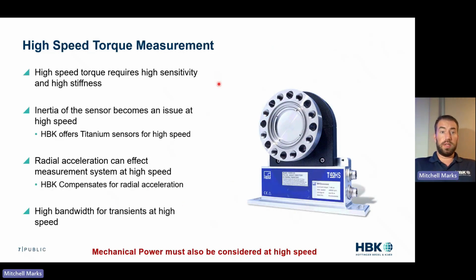High-speed torque measurement is also quite difficult. As you go to higher speeds, you end up in this interesting scenario where you need something to withstand that high speed, so you need really high stiffness. You also need a high sensitivity, and those things are at odds with one another. So measuring torque at a high speed is actually quite difficult. You also have the issue of the sensor inertia. The sensor is quite heavy at high speeds. It can actually throw off the dynamics of the system.